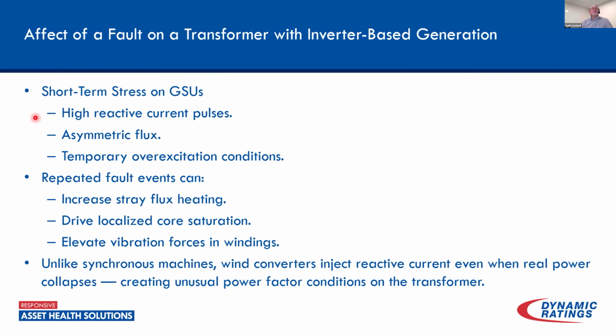The other thing that happens with inverter-based generation is, again, it's a very reactionary system. If I have a fault on the system, it's not uncommon to start injecting high levels of reactive current to try to keep the voltage up during that fault. Of course, when the fault subsides, if we're still producing that high reactive, a lot of VARs on the system, that can result in short-term voltage spikes and things like that on the system, which could distress our insulation.